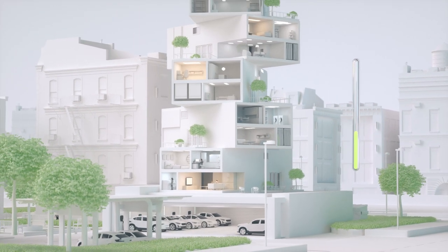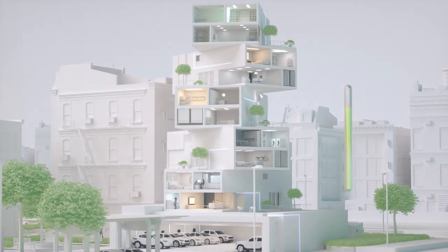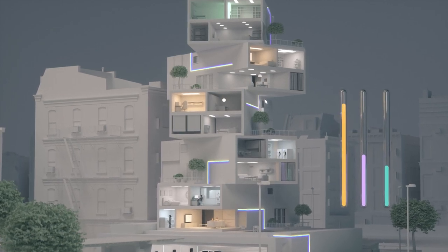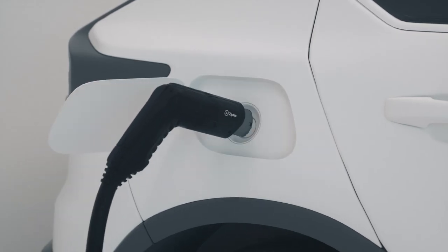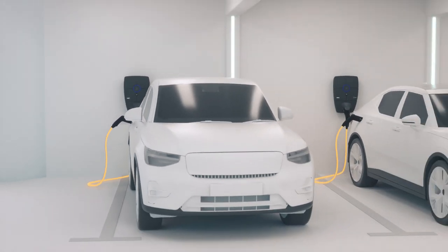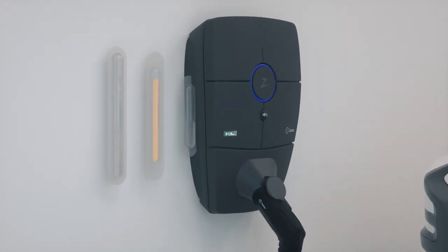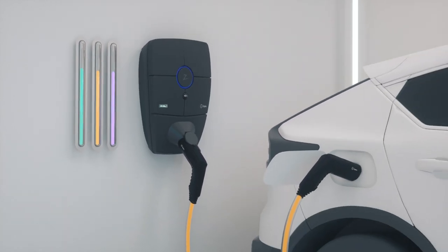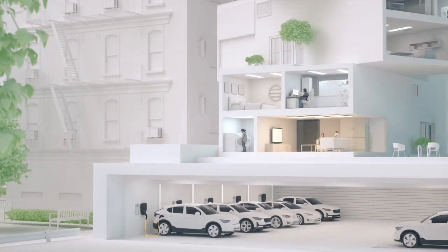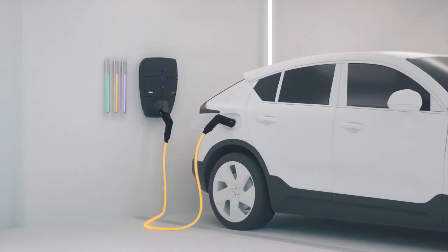Step 2 involves Zaptec's patented dynamic phase balancing. Every building has three power phases, but consumption is rarely perfectly balanced between them. Since many EVs charge on just one phase, you risk throttling charging speeds when many cars happen to charge on the same phase. With our dynamic phase balancing, it's as if we physically move cars around the parking lot to utilize all three phases evenly. It happens automatically, and we can also switch between one and three phase charging.